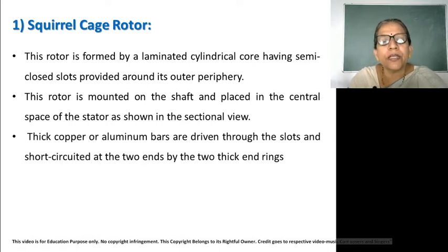What material are we using for the rotor winding? As far as the stator is concerned, it has a distributed winding and the material is essentially copper. But in the case of the rotor, we are using thick bars. So if it is a squirrel cage rotor, either thick copper or aluminum bars are driven through the slots.